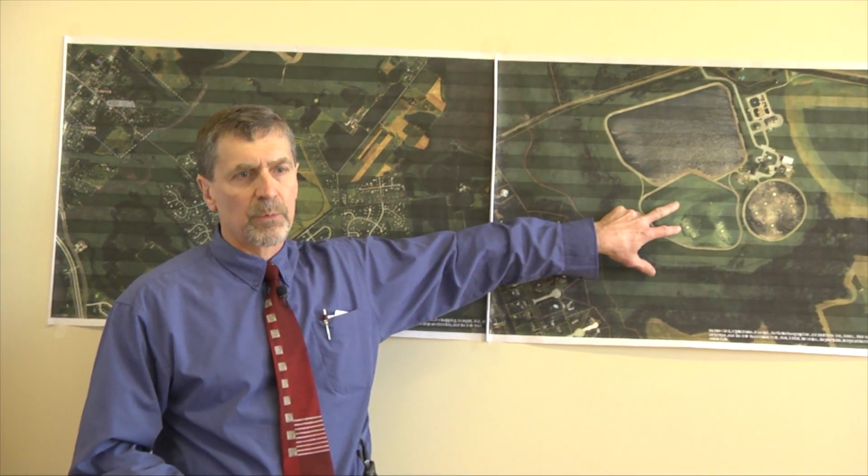Part of that cleanup required us to enhance the treatment process at this facility. So in 2005, we commissioned a mechanical extended aeration plant here called an SBR, which stands for Sequencing Batch Reactor. It's a mechanical plant that provides a much higher and much more controlled level of treatment, which restores our ability to discharge to the Appoquinimink River. With the lagoon treatment process, we almost had to stop discharging to the river. With the enhanced treatment process, we were able to restore our discharge and keep going to the Appoquinimink River.